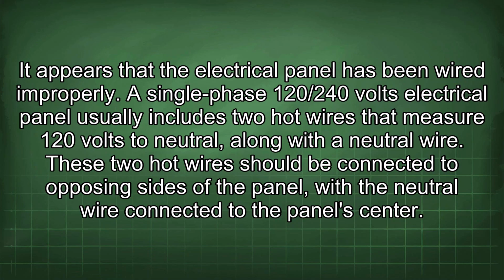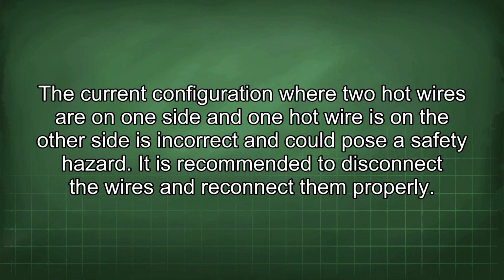It appears that the electrical panel has been wired improperly. A single-phase 120/240 volts electrical panel usually includes two hot wires that measure 120 volts to neutral, along with the neutral wire. These two hot wires should be connected to opposing sides of the panel, with the neutral wire connected to the panel's center. The current configuration where two hot wires are on one side and one hot wire is on the other side is incorrect and could pose a safety hazard.